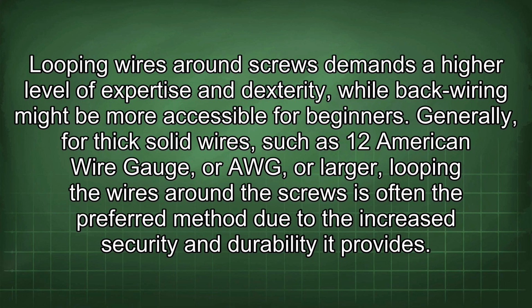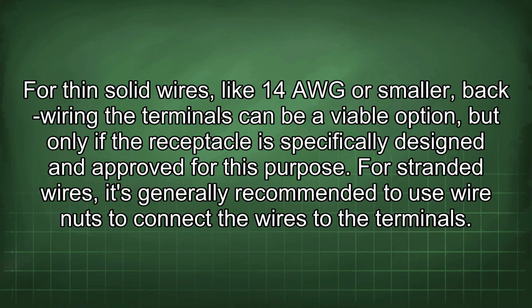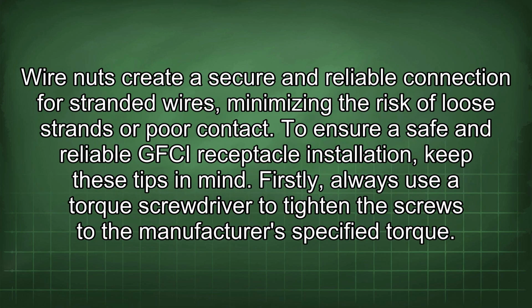Generally, for thick solid wires, such as 12 American wire gauge, or AWG, or larger, looping the wires around the screws is often the preferred method due to the increased security and durability it provides. For thin solid wires, like 14 AWG or smaller, backwiring the terminals can be a viable option, but only if the receptacle is specifically designed and approved for this purpose. For stranded wires, it's generally recommended to use wire nuts to connect the wires to the terminals. Wire nuts create a secure and reliable connection for stranded wires, minimizing the risk of loose strands or poor contact.